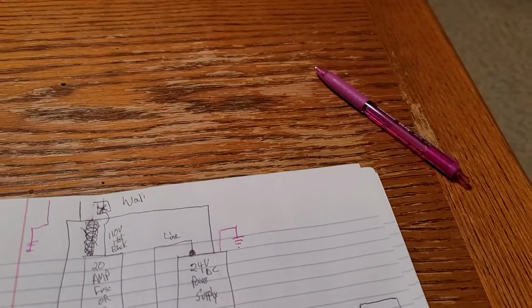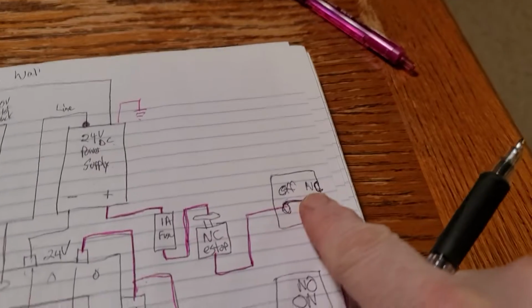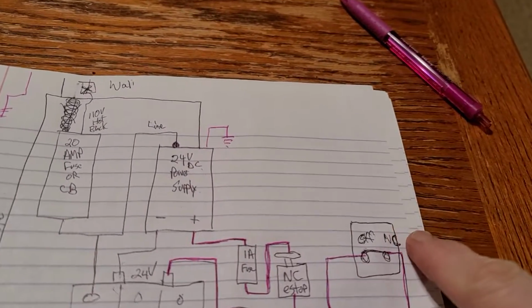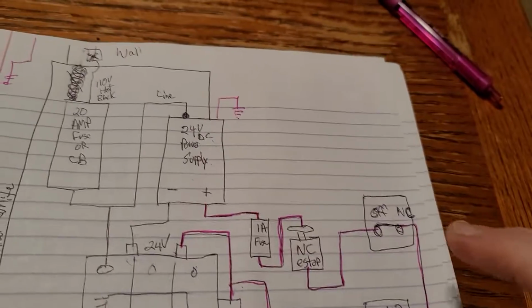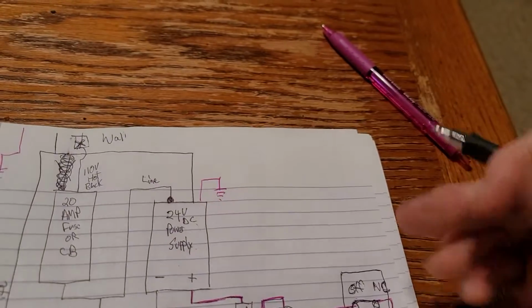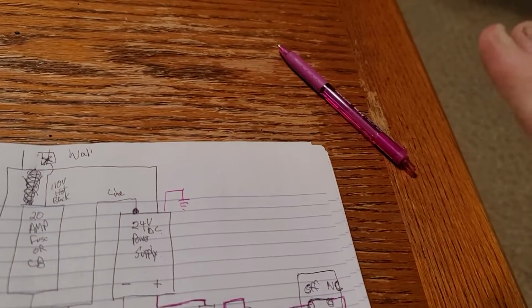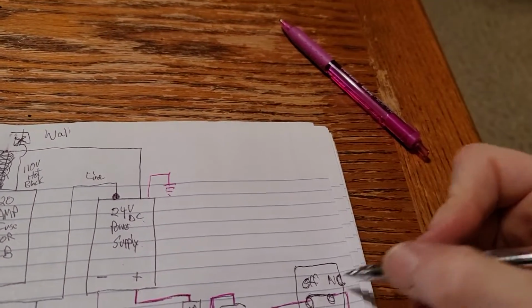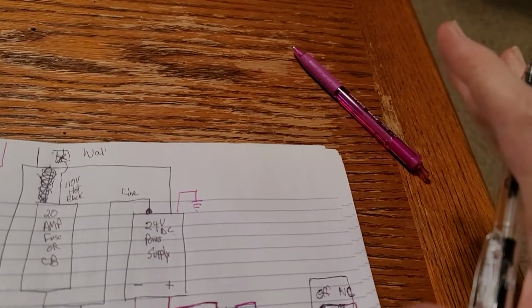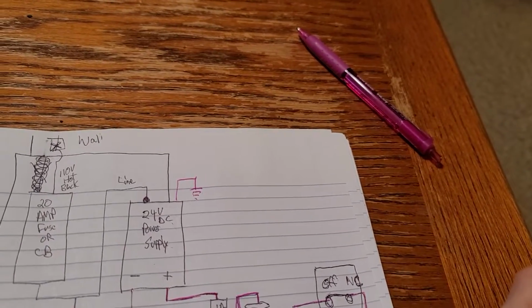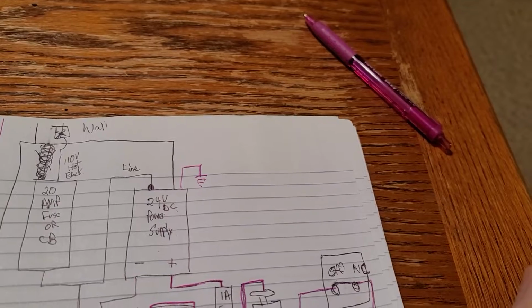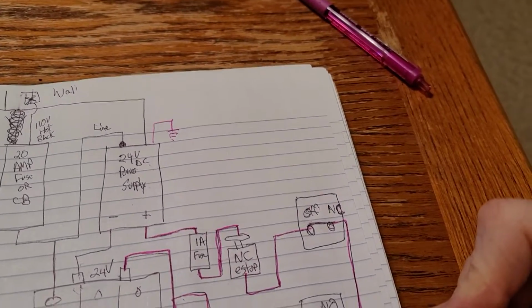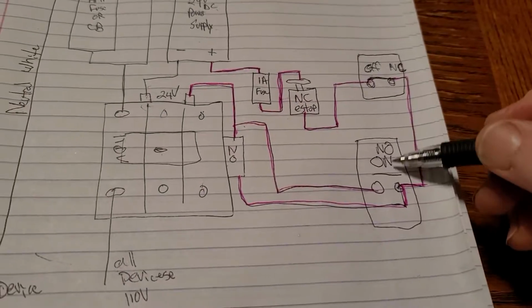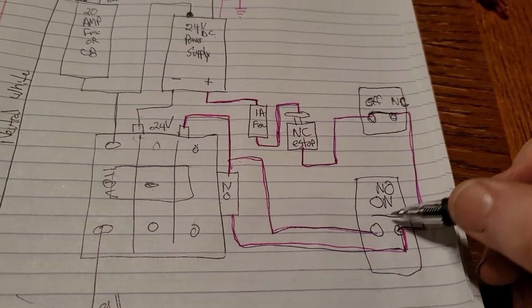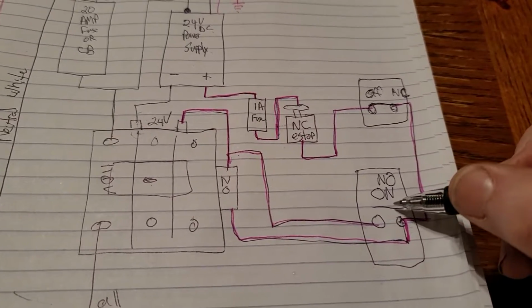And so what this means is the 24 volts is going through the off button all the time, right? Until you press the off button, at which point the spring opens in this. That's why I say it's normally closed. When you press it, it becomes open. Power is always going through it. And it's going here to the on button, one side, okay? One side of the on button. The on button is normally open. That's why the line's drawn at the top, right?